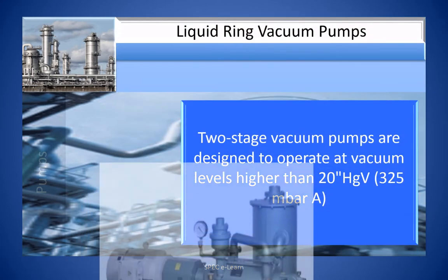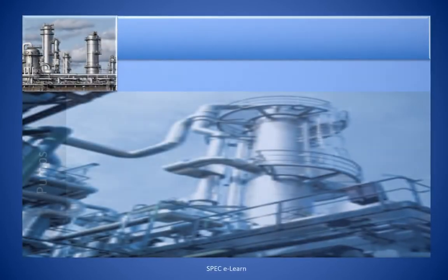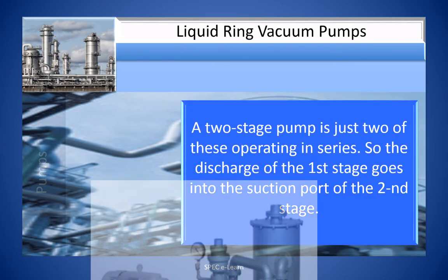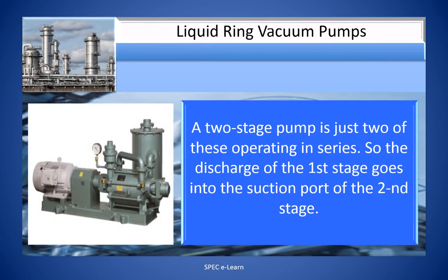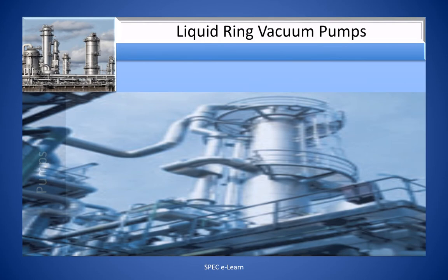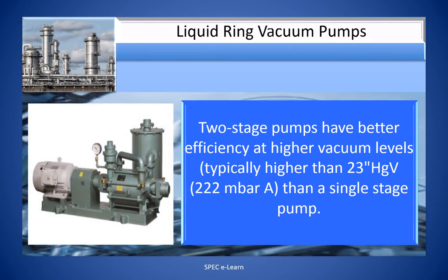Two-stage vacuum pumps are designed to operate at vacuum levels higher than 20 inches of mercury vacuum. A two-stage liquid ring pump is just two single stages operating in series, so the discharge of the first stage goes into the suction port of the second stage. Two-stage pumps have better efficiency at higher vacuum levels, typically higher than 23 inches Hg vacuum, than a single-stage pump.